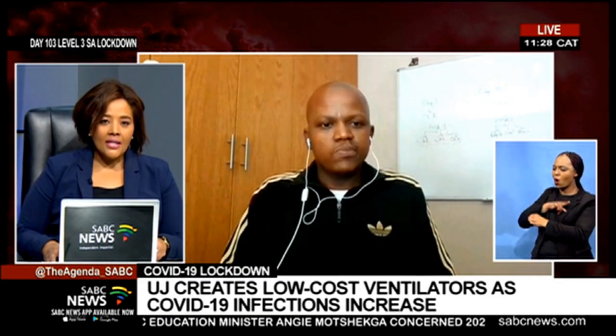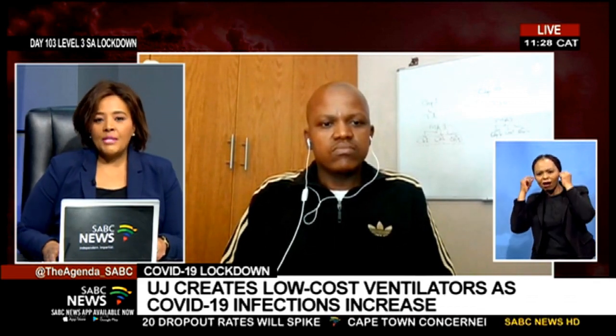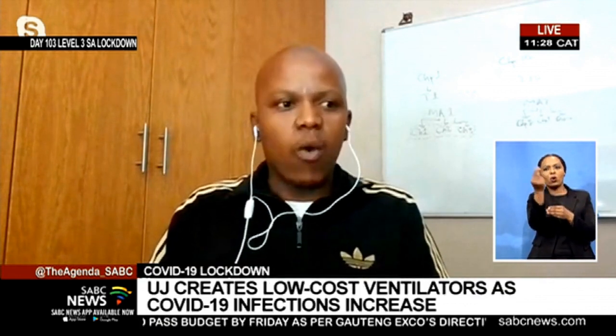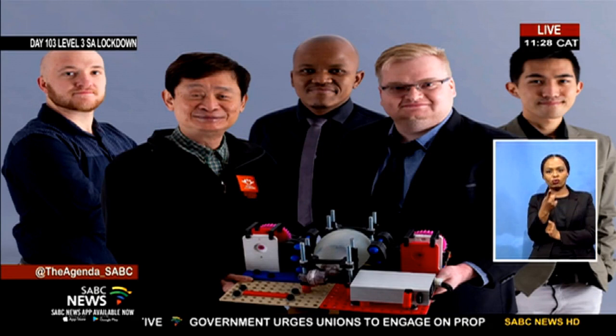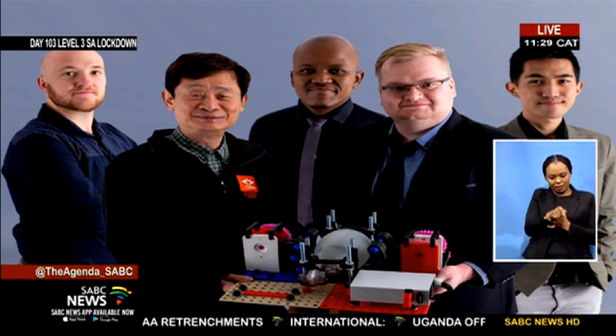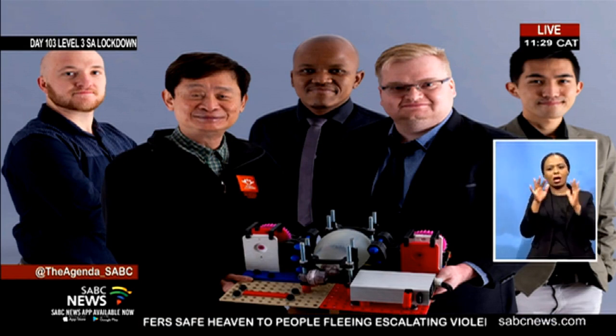It also solves another big problem in the fight against COVID-19, where the health sector was worried about people sharing ventilators. What we've done with the design is that we have adopted a very basic concept of the LEGO design, so the base plate actually enables one to have two ventilators mounted side by side. That also makes it easy for patients to access this. And because we sometimes have challenges with electricity supply in South Africa, we've also mounted lithium power batteries so that these devices can be operated without the need for electrical connections.